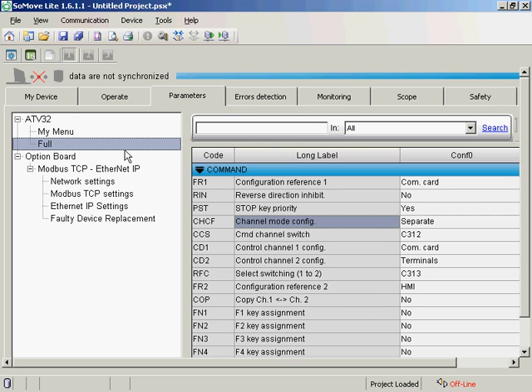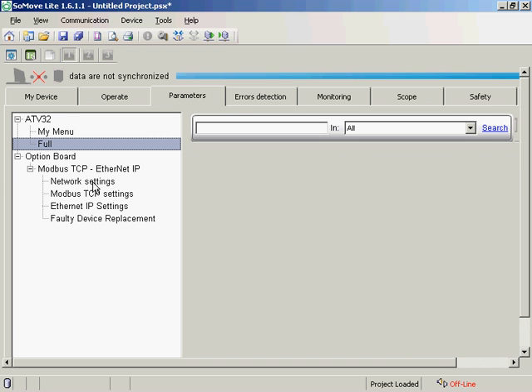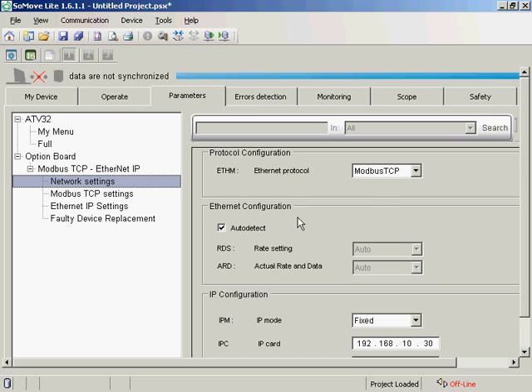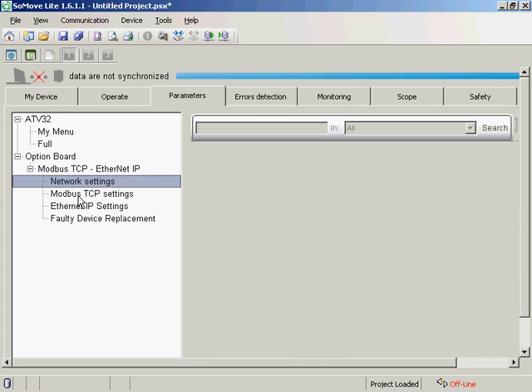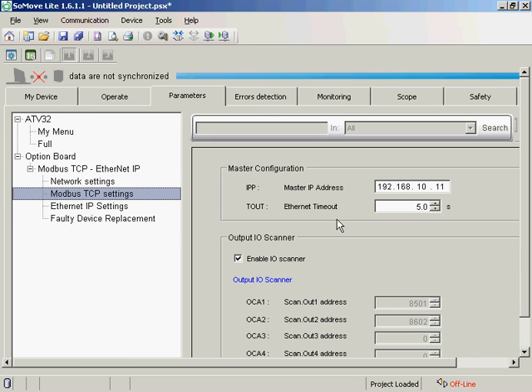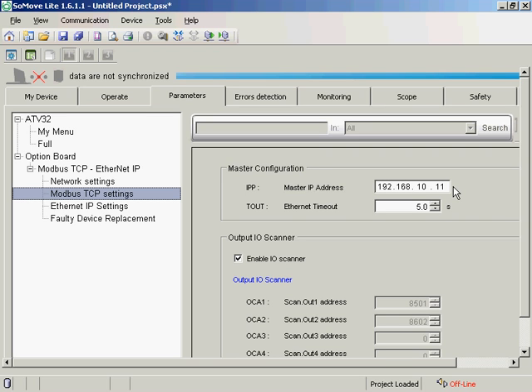We're going to control the reference speed via the com card or via the HMI on the ATV32. We're using Modbus TCP, and our IP address is 192.168.10.30. Modbus TCP settings: we are enabling the I.O. scanner. We're using the default addresses, and the master IP address is 192.168.10.11 with a five-second Ethernet timeout. The drive will fault out if it loses coms for five seconds or more. When the drive does fault out, it will stop.